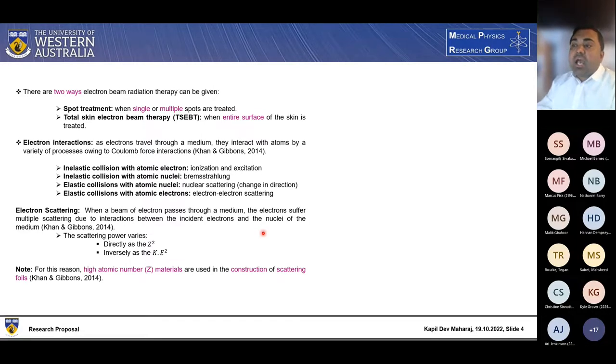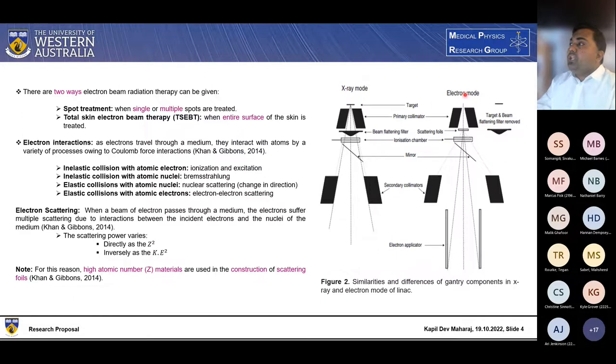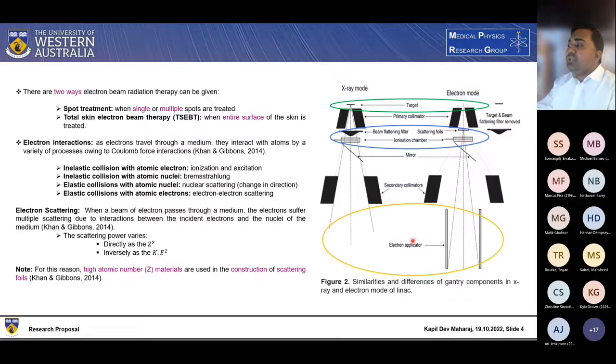Because of these two points, we usually use a high atomic number material for constructing the scattering foils. So in terms of the differences between the linear accelerator mode for photon and electron beam, in electron beam, we retract the target. And second main difference is that instead of using the beam flattening filter, we use an electron beam scattering foil to further scatter the electron beam. And in the end, we use the applicator to further shape the field size of the electron beam. So these are the three key differences which we observe in terms of the mode of X-ray mode and electron mode in linacs.